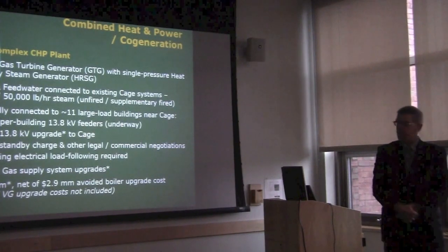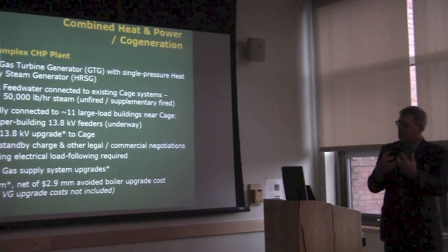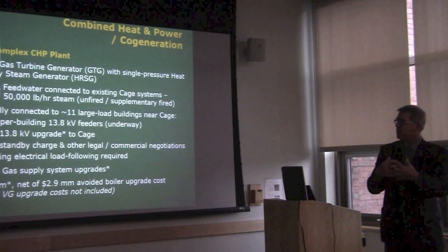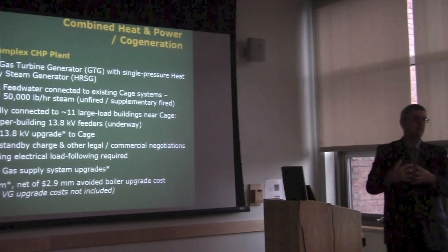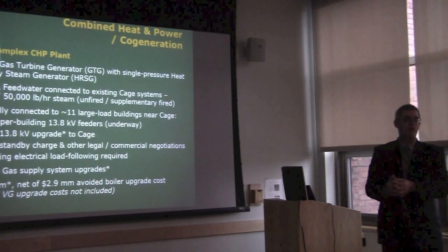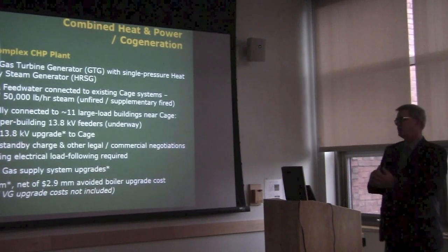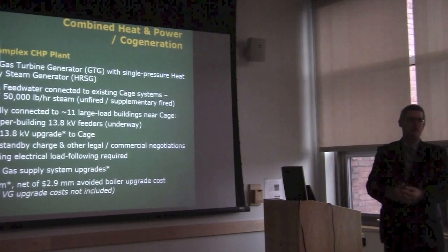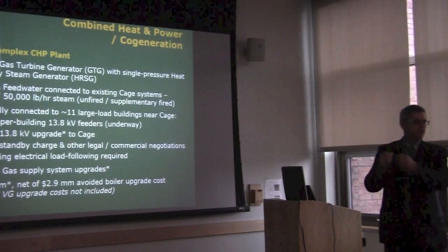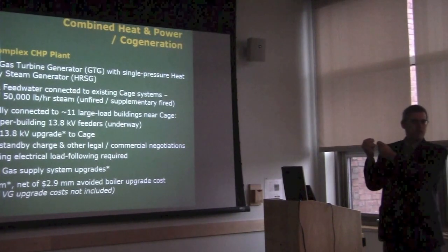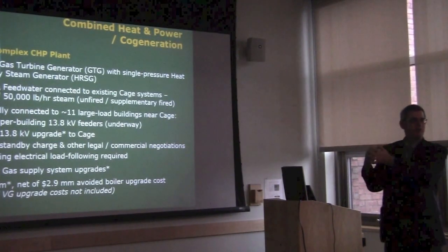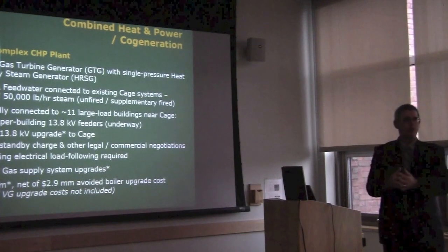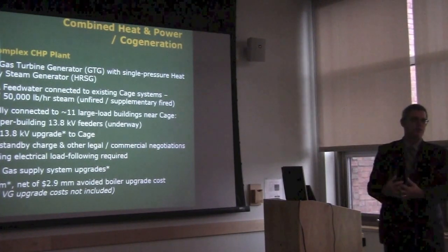There's another curious thing: because we're only feeding 11 buildings and we're not really allowed to export any additional power out to the grid, it will have to be an electrical load-following system. In other words, we may think we can make 3.5 megawatts, but if the 11 buildings only need 3.2 megawatts, we have to run at 3.2.